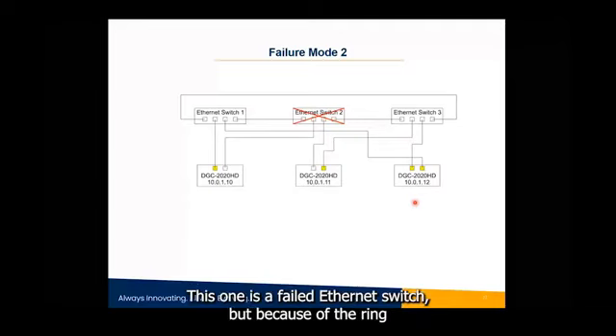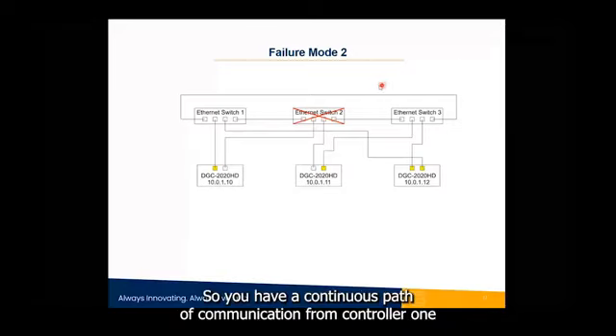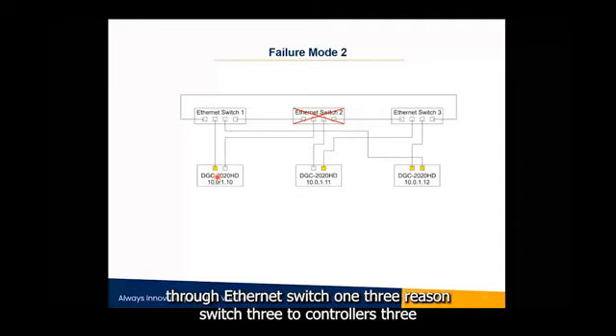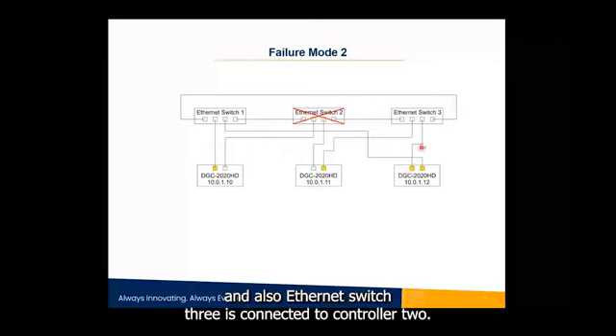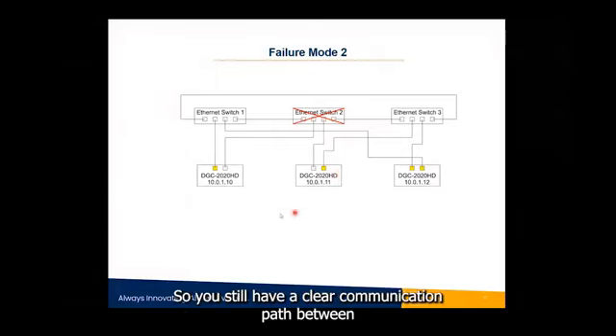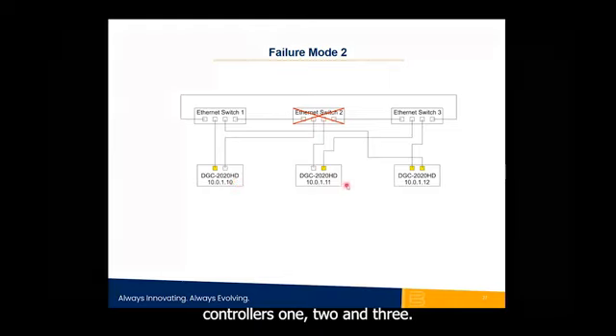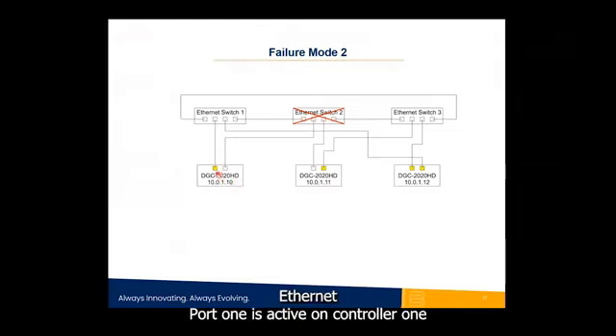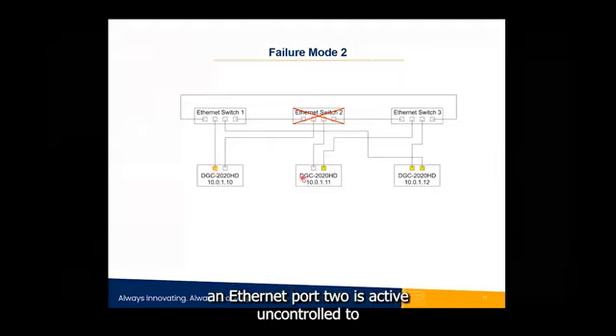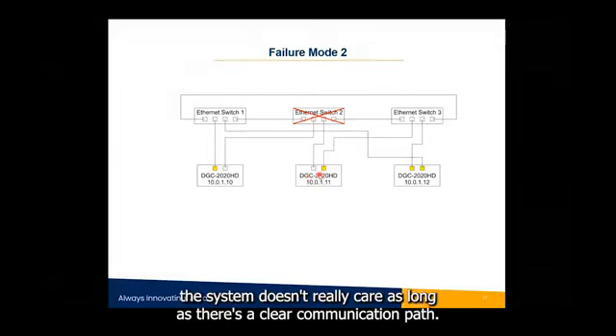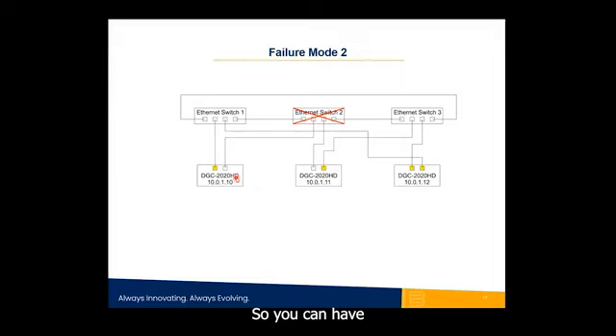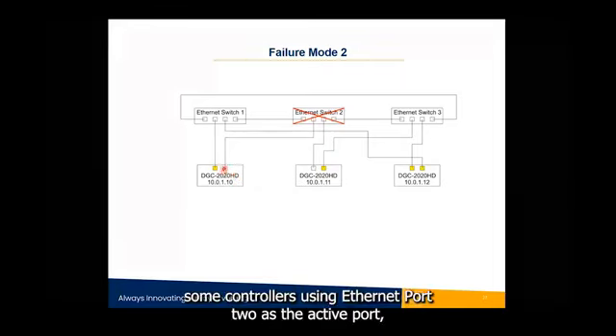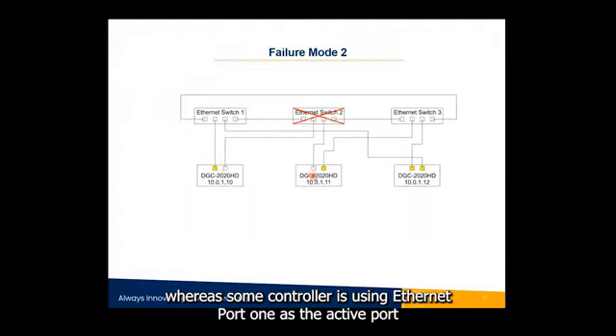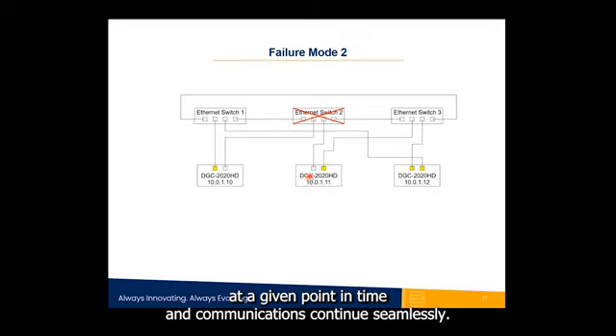Here's another failure example. This one is a failed Ethernet switch, but because of the ring network, Ethernet switches 1 and 3 are still connected, so you have a continuous path of communication from controller 1 through Ethernet switch 1 through Ethernet switch 3 to controller 3, and also Ethernet switch 3 is connected to controller 2. So you still have a clear communication path between controllers 1, 2, and 3. It doesn't matter if Ethernet port 1 is active on controller 1 and Ethernet port 2 is active on controller 2. The system doesn't really care as long as there's a clear communication path. So you can have some controllers using Ethernet port 2 as the active port, whereas some controllers are using Ethernet port 1 as the active port at a given point in time, and communications continue seamlessly.